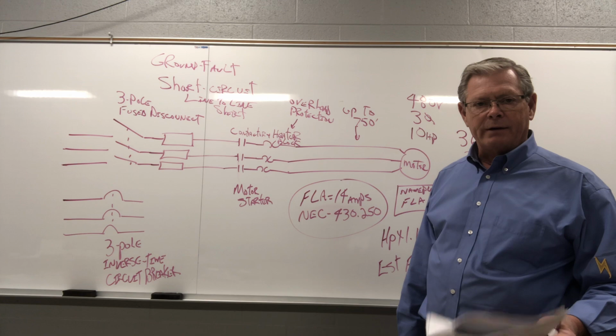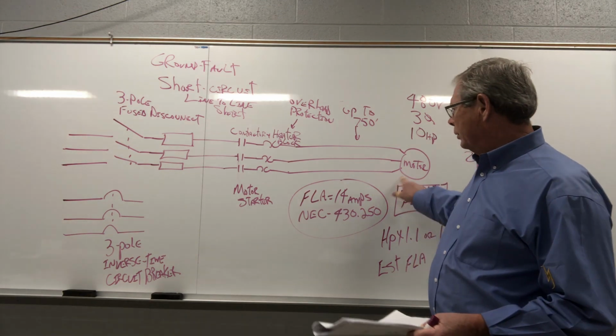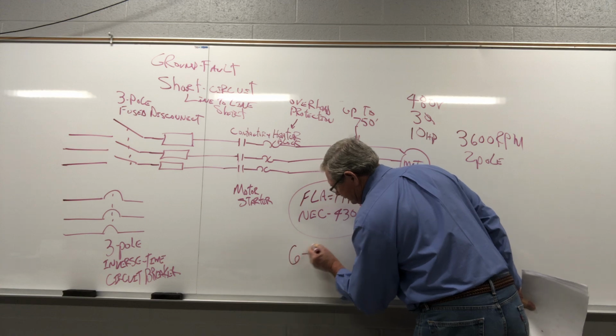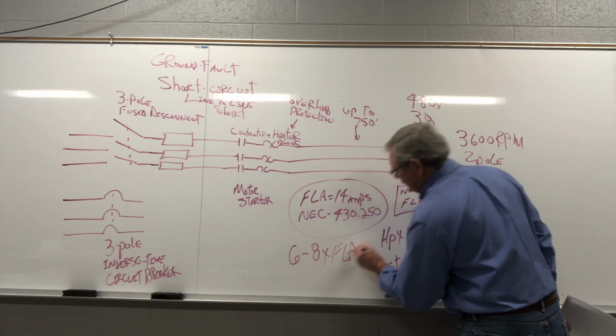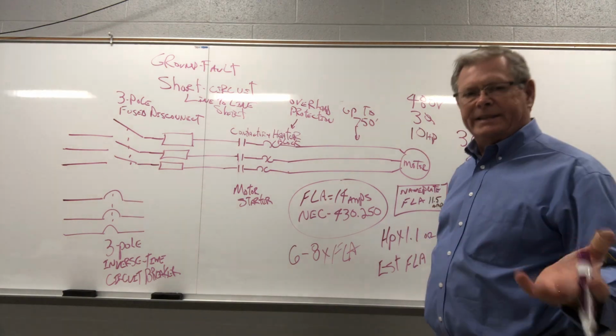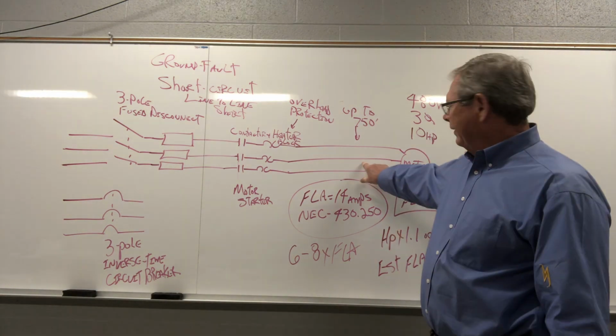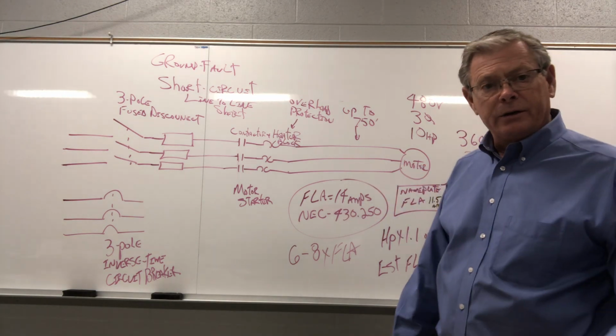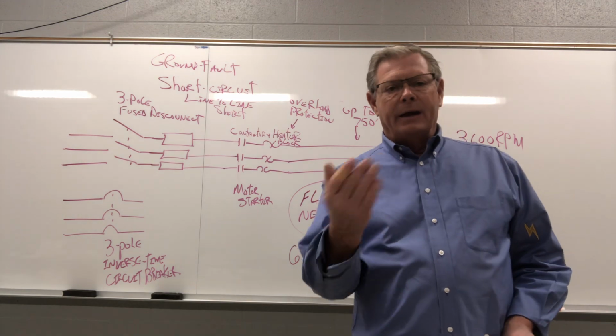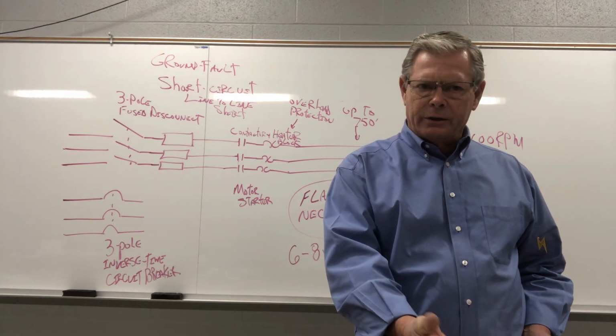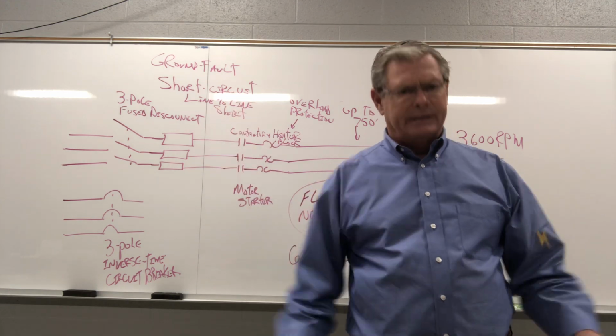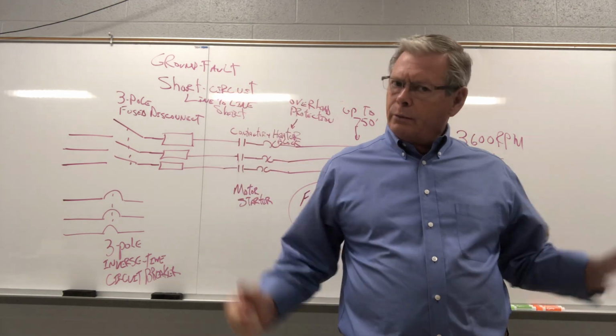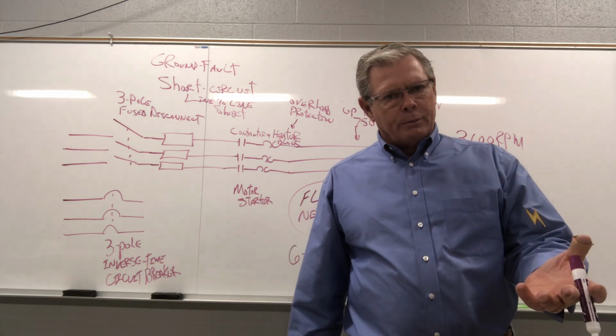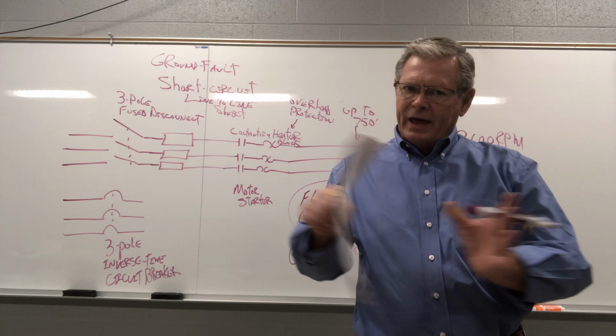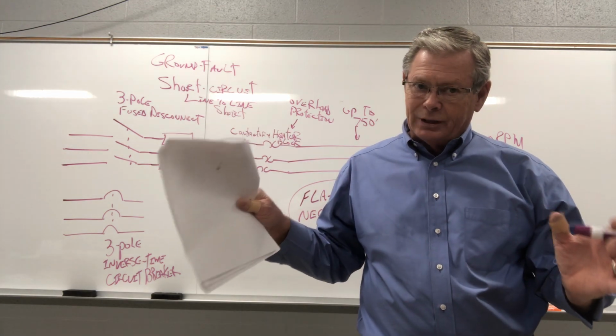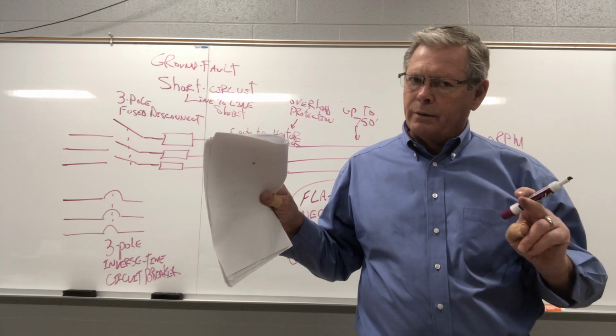Think about what happens whenever you start a motor. That motor is going to pull 6 to 8 times FLA, right? So if we were to do the math, we're pulling 60 to 90 amps on this circuit to start. So what's that going to do to the wire? It's going to heat it up. Now it depends on whether we have a high inertia or a low inertia load. High inertia load is going to be like a flywheel. It's going to sit there, and when you hit the motor start, it's going to turn a lot of weight. It's going to take a while to get going. Take a chemical pump or something, it just whoom. So that has a bearing on how long that 60 to 90 amps last. So it's during that time that we're going to be heating that wire up.